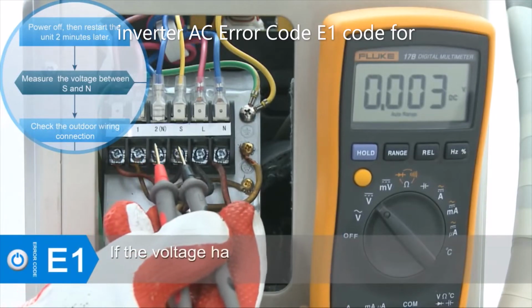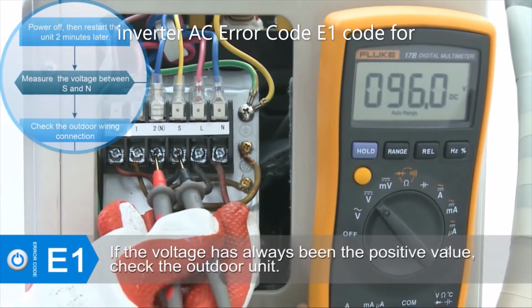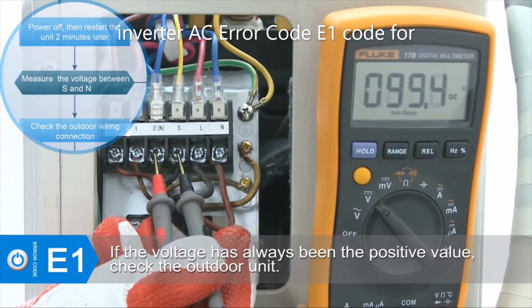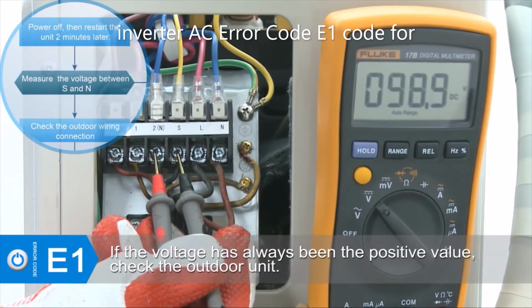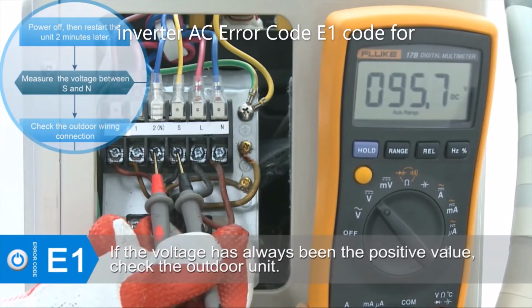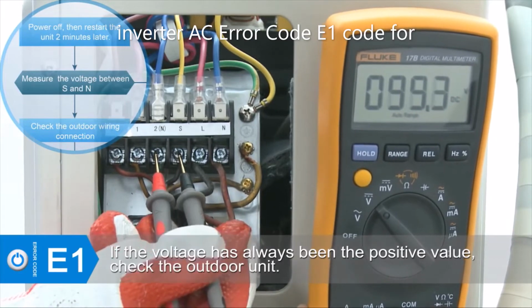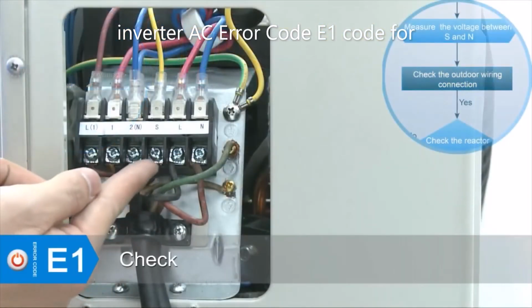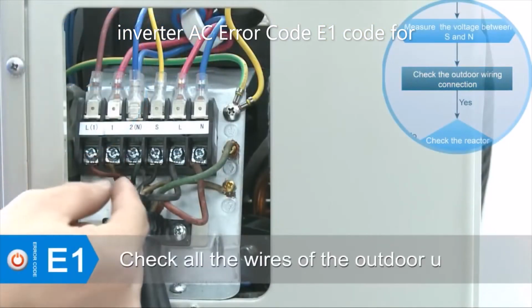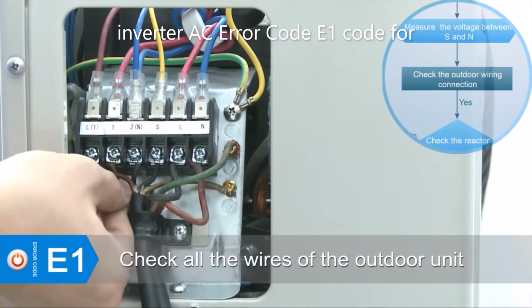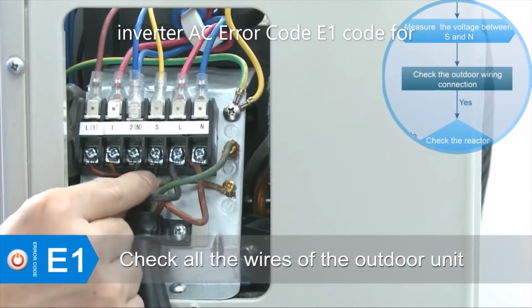If the voltage has always been the positive value, possible malfunction may have occurred on the outdoor unit. Main attention should be paid to the outdoor unit. Check the wiring of the outdoor unit, which includes the power wires and the connecting wires between the indoor and the outdoor unit.